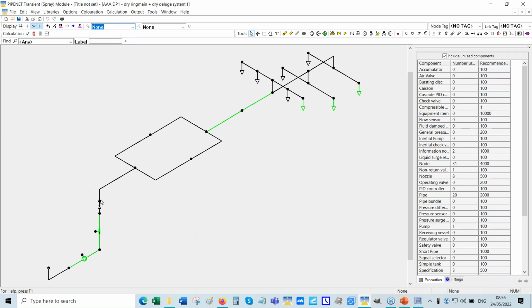First thing you notice here is that there is no overboard dump system, because purely from the point of view of the system startup, the air from the caisson can simply go into the dry fire watering main and the dry deluge system and simply go out. You don't need an air release valve here. And that's why the model is like that.